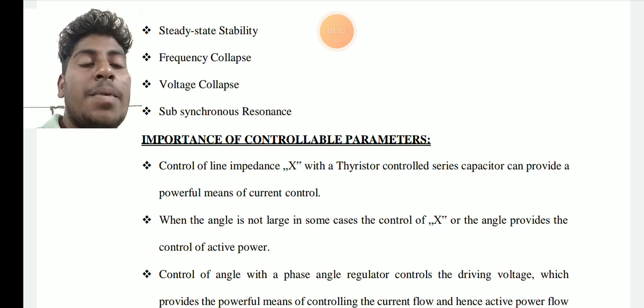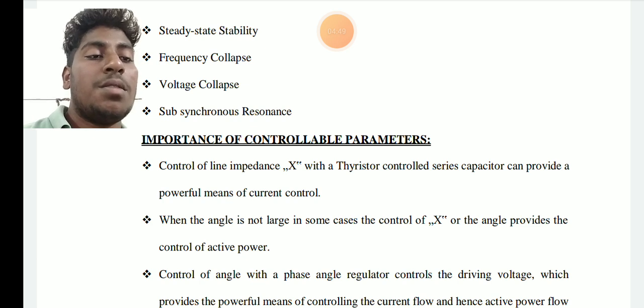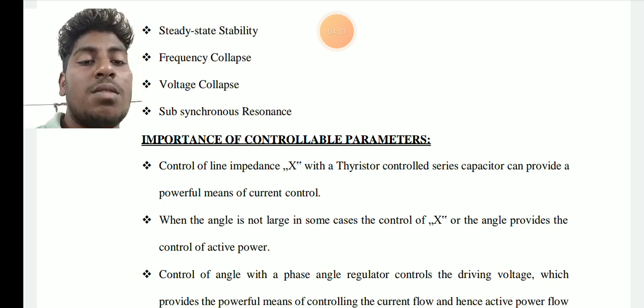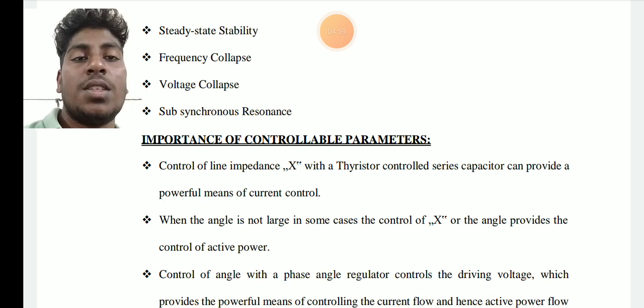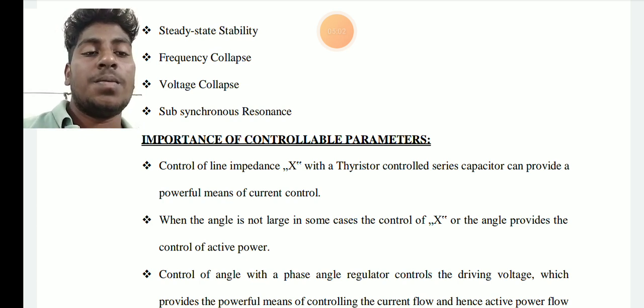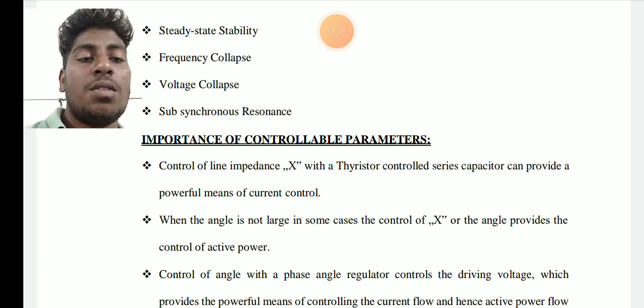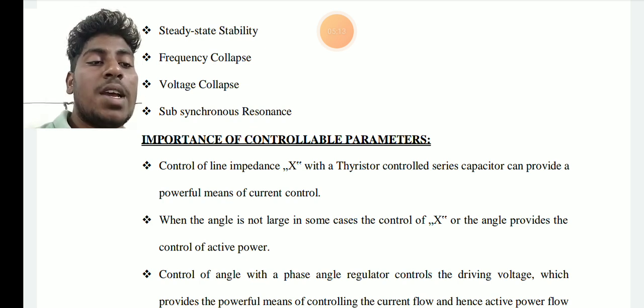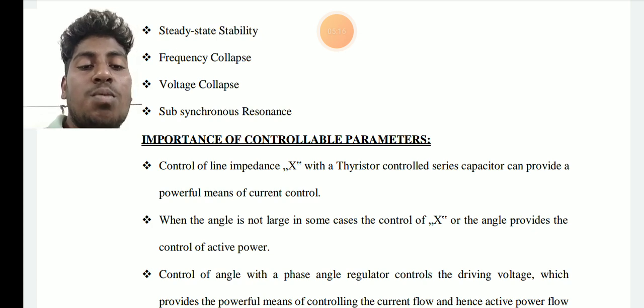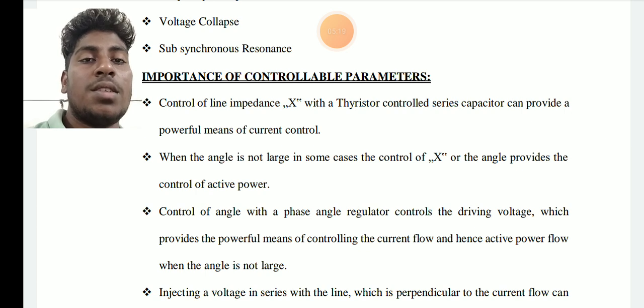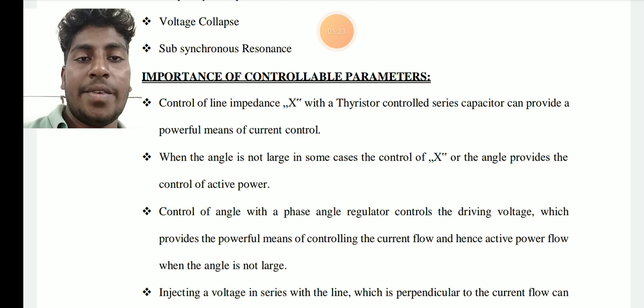Control of line impedance X with thyristor controlled series capacitors can provide a powerful means of control when the angle is not large. In some cases, control of X or the angle provides a means to control active power. When a phase angle regulator is used, it is very effective, and these are a powerful means of controlling the current flow and hence the active power flow when the angle is not large.